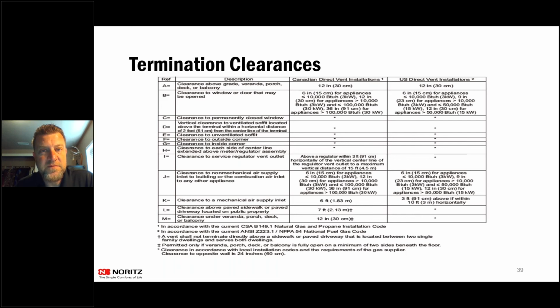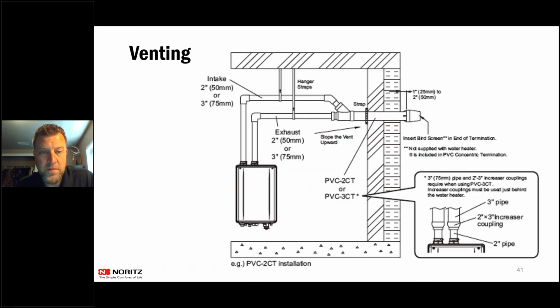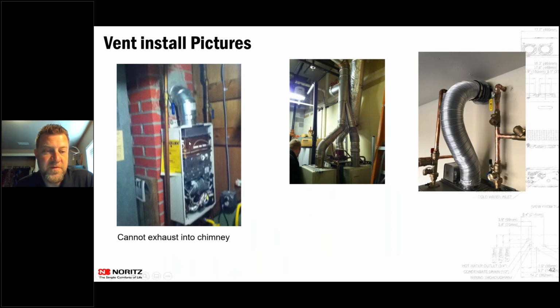Okay, the picture you had, did it not have any venting? Yes, that one there, it would send it into the chimney. It just has that P-Vent 90 where they put a hole in the brick and then just masked it off. So it was just atmospherically venting into that chimney. Okay, with no liner or anything inside that chimney. Gotcha. What's the purpose for not being able to do that?